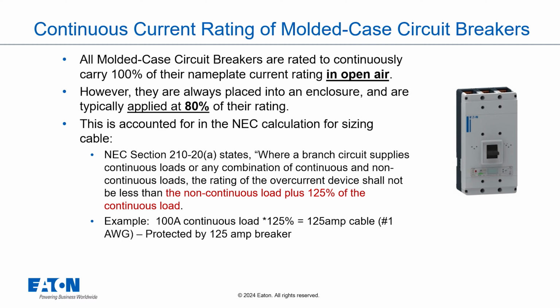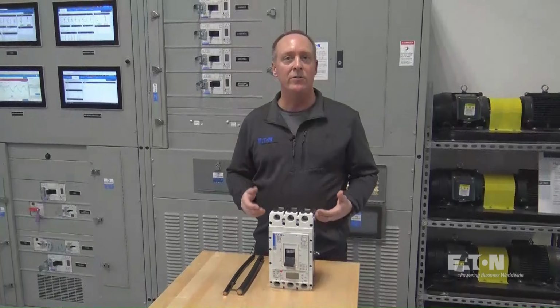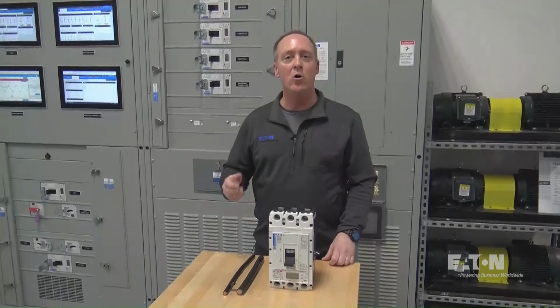Per the National Electric Code, cables are sized to the given load. Typically, the continuous load is multiplied by 125% in order to come up with the appropriately sized cable, and then the circuit breaker is matched to that cable size. So for example, we take a 100 amp load, multiply that by 125%, because that's its continuous current rating, I get a 125 amp rated cable, and then a 125 amp circuit breaker is applied.